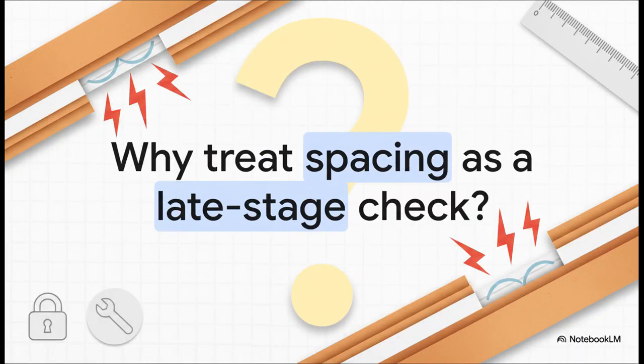So think about your own engineering workflow for a second. Why do we still treat spacing as a late-stage check? Honestly, it's a fundamental flaw in how a lot of panels are built. In the real world, electrical clearance and creepage distance absolutely must be set way before you freeze your copper routing or your enclosure designs. If you try to shoehorn these safety parameters in after the physical geometry is locked, oh man, you are setting yourself up for a really bad time.